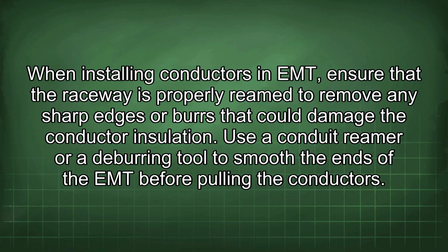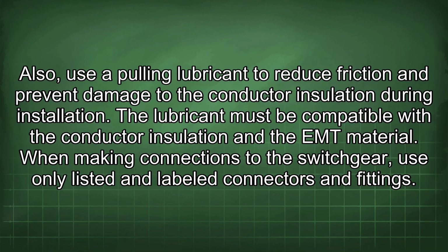When installing conductors in EMT, ensure that the raceway is properly reamed to remove any sharp edges or burrs that could damage the conductor insulation. Use a conduit reamer or a deburring tool to smooth the ends of the EMT before pulling the conductors. Also, use a pulling lubricant to reduce friction and prevent damage to the conductor insulation during installation. The lubricant must be compatible with the conductor insulation and the EMT material.